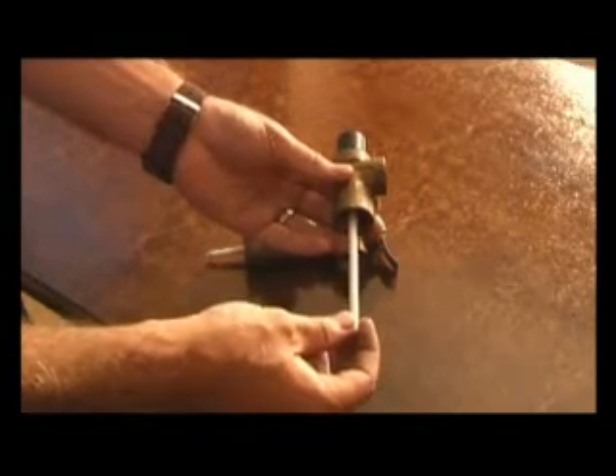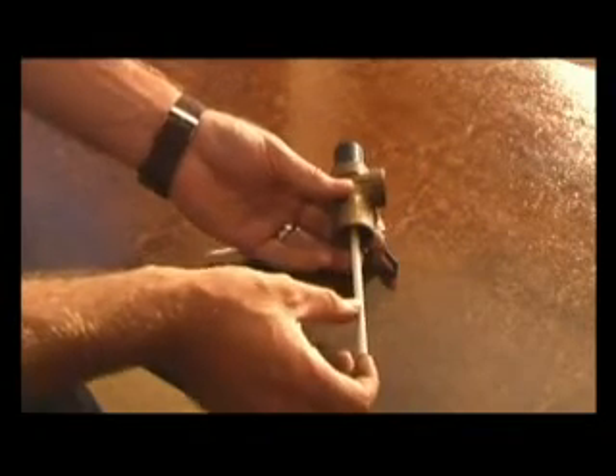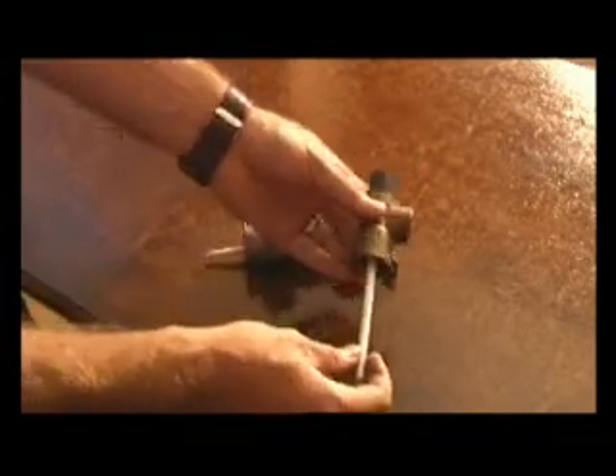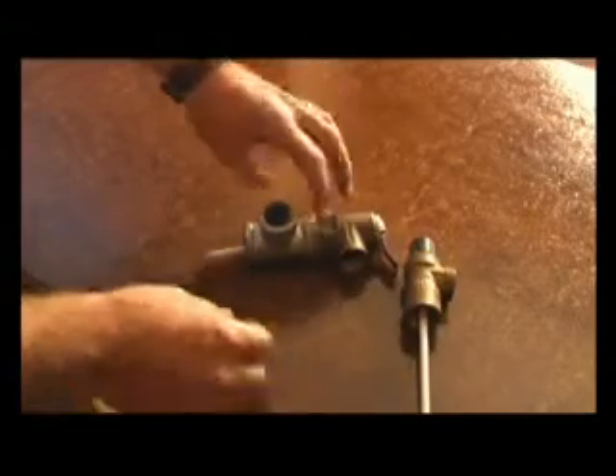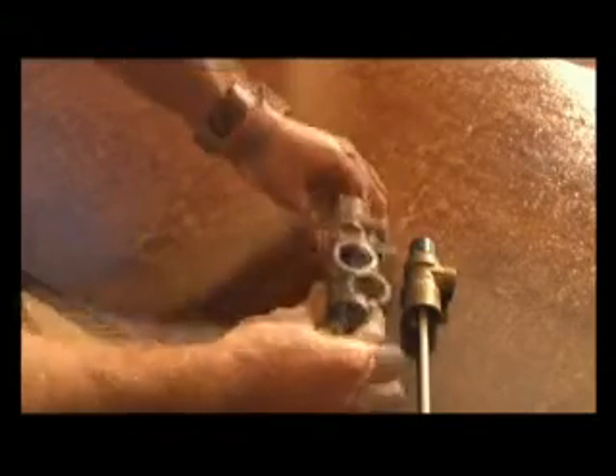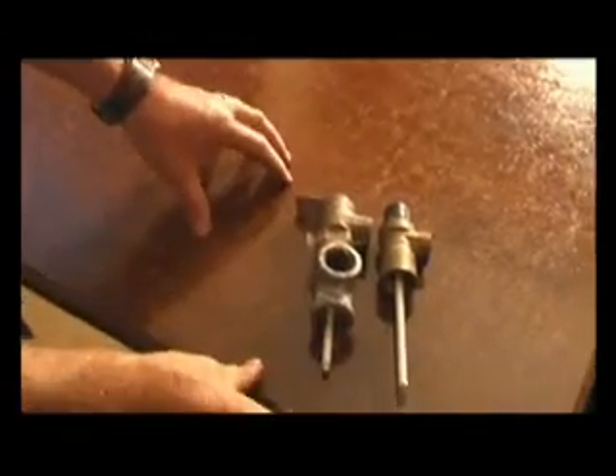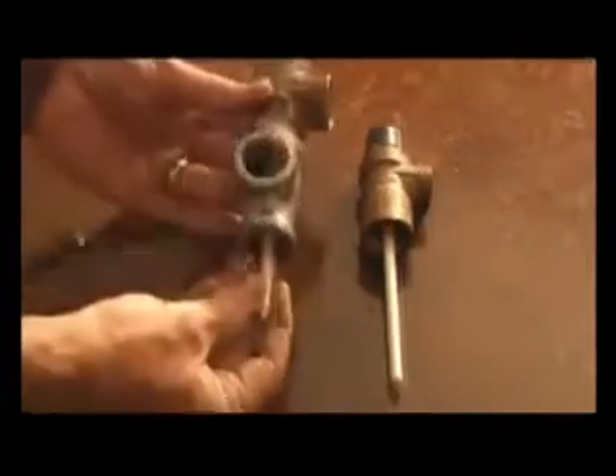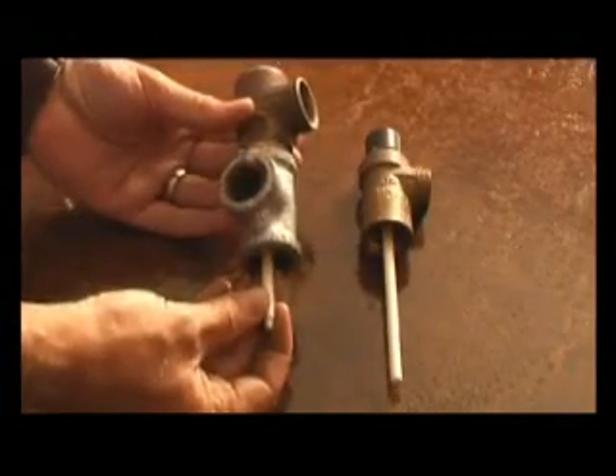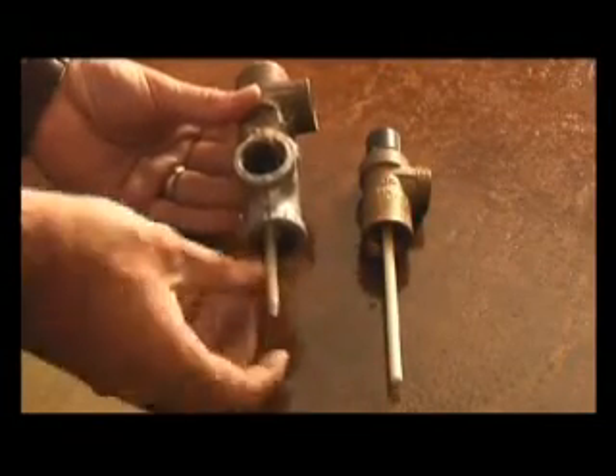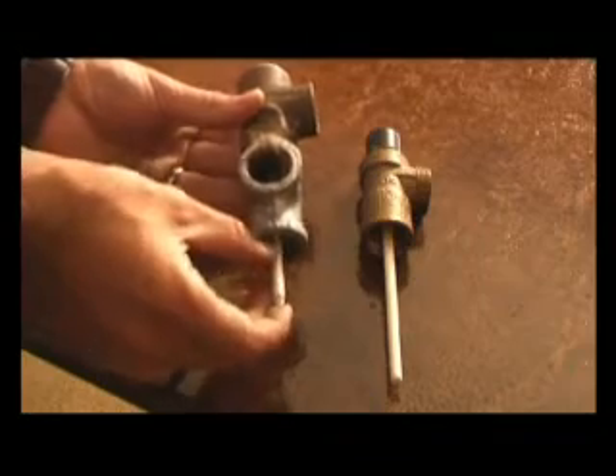SANS 10254 states that the probe of the T&P valve needs to be a minimum of 25% of the length of the valve inside the body of the water being heated. In this case you can see somebody tried to make an extra port on the geyser, and this probe will not enter the geyser as needed.